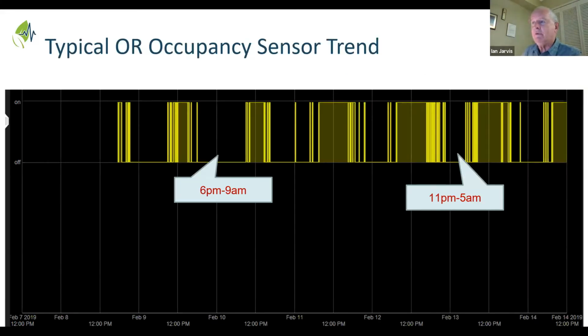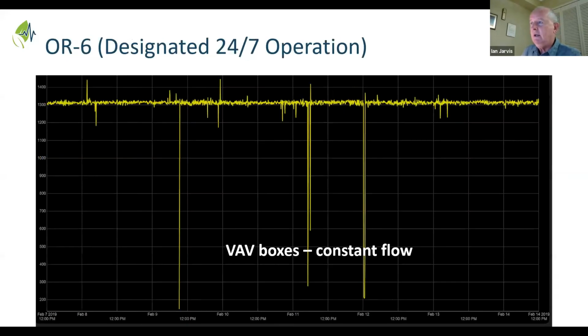Once this is up and running, it's always fun looking at the trend logs. You can see immediately for a typical controlled operating room what the unoccupied periods look like. They change from day to day and week to week, but those are the periods when the airflow can be set back.